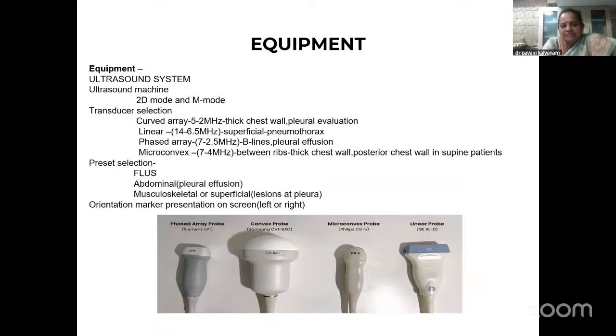We have the ultrasound machine. Any basic ultrasound machine can be used, and the 2D mode and the M mode, if they are there in the ultrasound machine, that is enough. For transducer selection, any of the transducers can be used: the curved array, the linear, the phased array, or the microconvex. For preset selection, if the machine has a FLUS selection, you can use it. Or an abdominal preset can be used for the detection of pleural effusion, and musculoskeletal or superficial for the lesions at the pleura. And the orientation marker presentation on the screen can be either left or right.